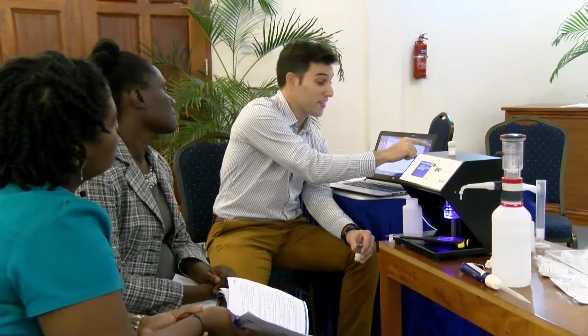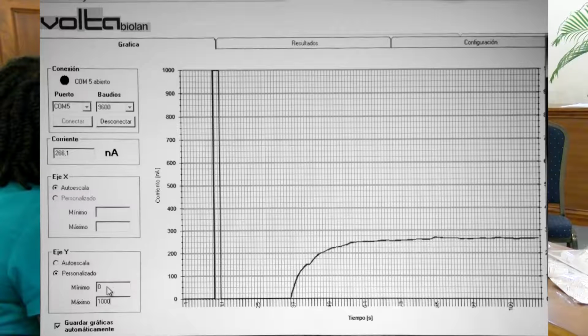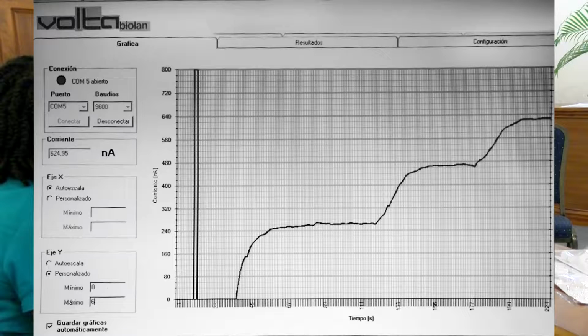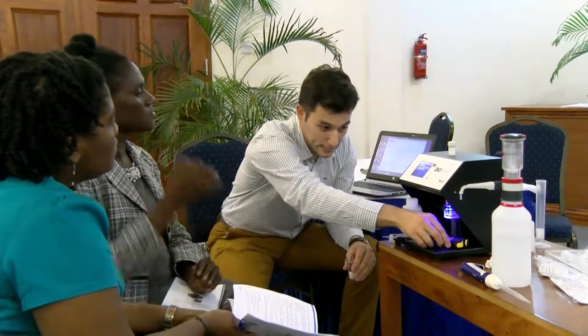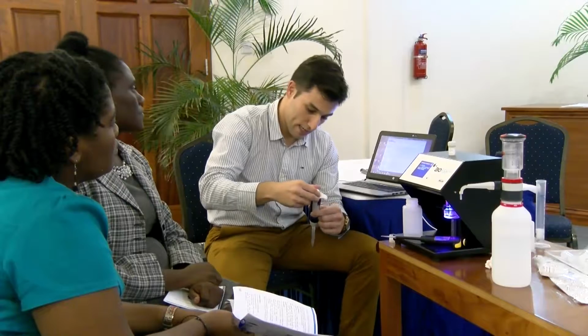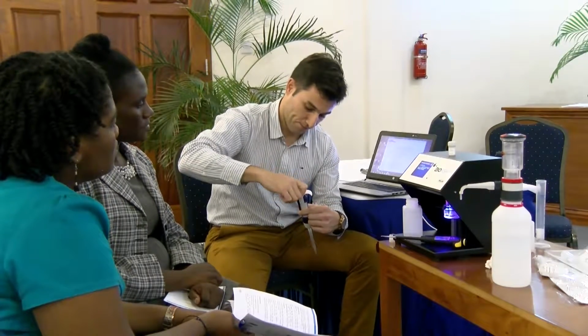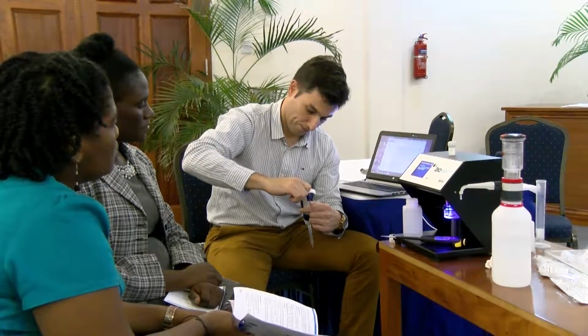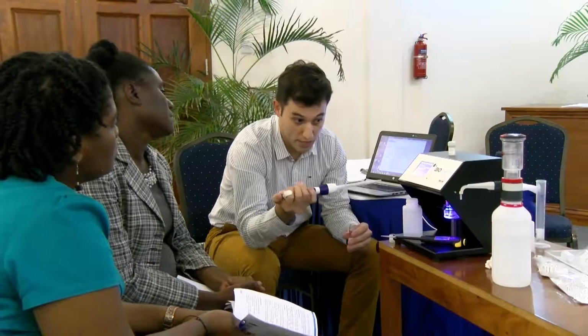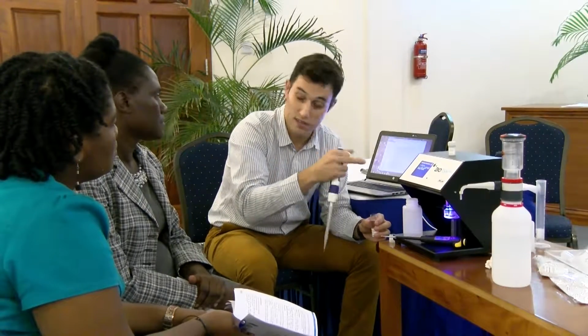We will add the same, 2 milliliters of the same calibration standard, and a second jump will occur. After the second jump, we will have 3 points: the zero point, the first stable condition, and the second stable condition. These 3 points will produce one calibration line. The slope of this calibration line will relate the intensity with the histamine concentration from now on, for the whole day. The quantity to add is the same, 2 milliliters of calibration standard, 2 times. In the sampling procedure it is the same, 2 milliliters of the extraction.